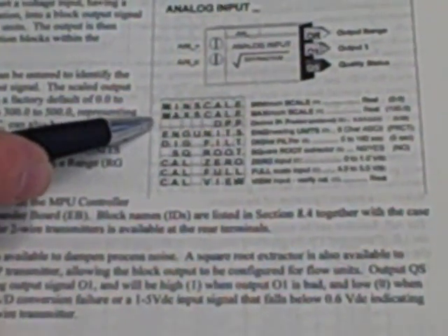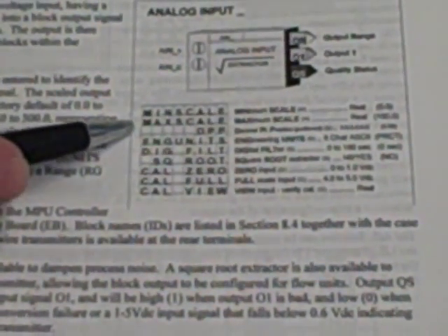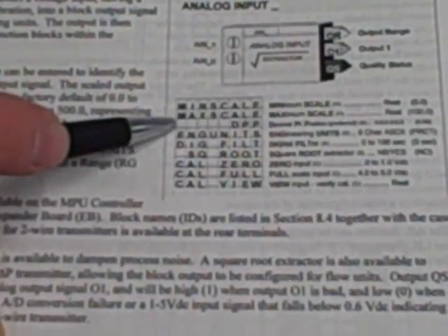We're going to turn to the alphabetized listing of all the function blocks. Analog input right here, we see the two parameters are min scale and max scale, equivalent to lower range value and upper range value respectively. We need to navigate to that block to those parameters and alter them.